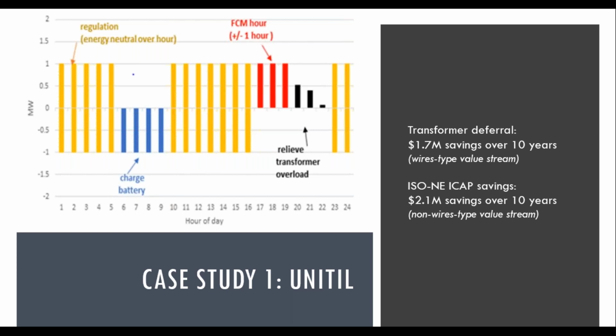A couple of things are interesting here. One is that the deferral is temporary - they're not replacing the substation upgrade forever, just deferring it for 10 years and claiming the savings on that. Storage can get you a lot of value in deferring this type of upgrade, but the battery itself is not a substation. If load ultimately grows past where it's economical to use storage to defer, you will eventually need that upgrade.